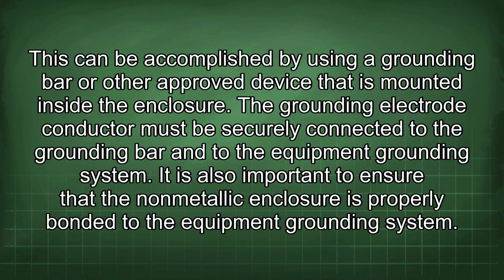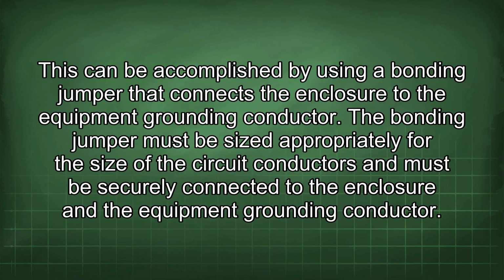It is also important to ensure that the non-metallic enclosure is properly bonded to the equipment grounding system. This can be accomplished by using a bonding jumper that connects the enclosure to the equipment grounding conductor. The bonding jumper must be sized appropriately for the size of the circuit conductors and must be securely connected to the enclosure and the equipment grounding conductor.